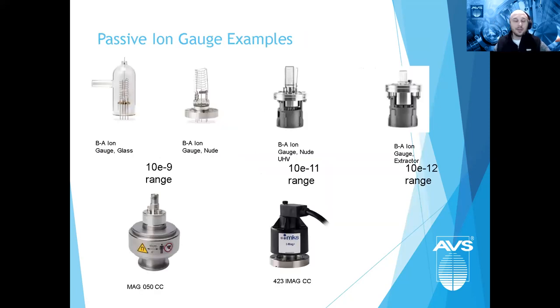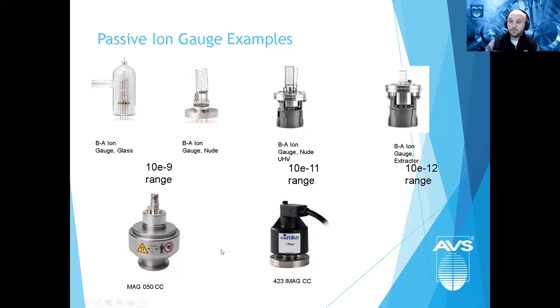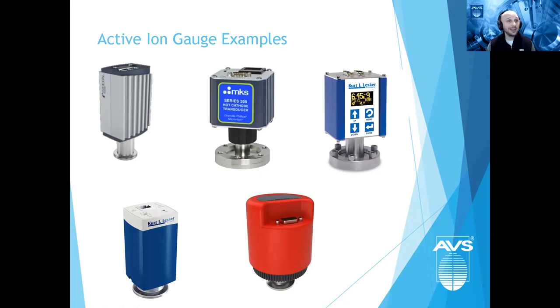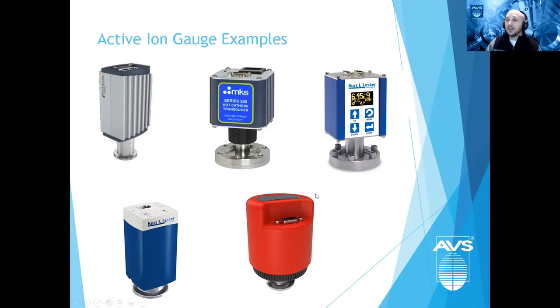There are different styles of hot filament ion gauges: Bayard-Alpert (BA) ion gauges, nude UHV, and extractor gauges which get you very low in vacuum. There are also passive cold cathodes. Active ion gauges come with serial communications, integrated displays, analog outputs, EtherCAT, Profibus, and more. If you need an integrated display or a specific communication interface, there's a manufacturer that has it. For drop-in replacements, you need to match the electrical connection and analog/digital output.